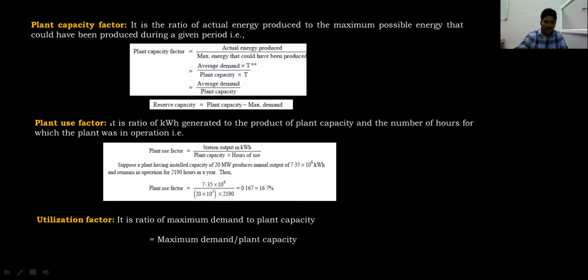Next one, plant use factor. It is the same as plant capacity factor, the only difference is the time. Whether the plant is operated for 365 days or not, for plant capacity factor we use 365 days into 24, 8760 hours. But here, if the plant is shut down for 10 or 15 days, say 10 into 24, the 240 hours need to be subtracted from 8760 hours and substituted here to obtain the plant use factor. So the only difference is in the term T. The plant is used for that many days, so we find the factor for those many days. That is plant use factor.